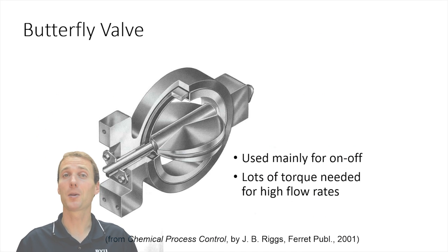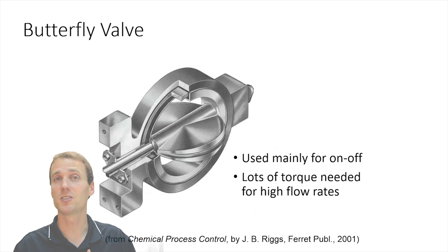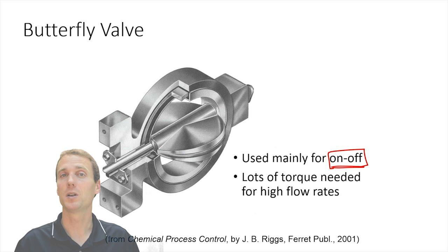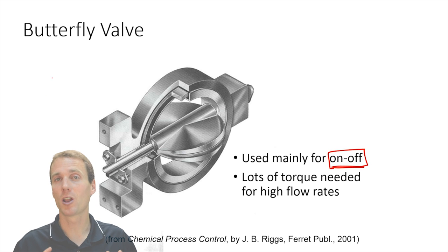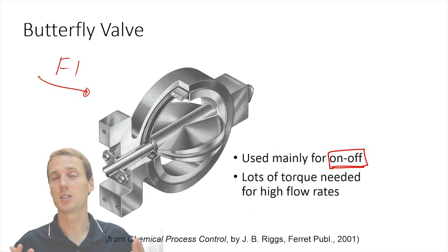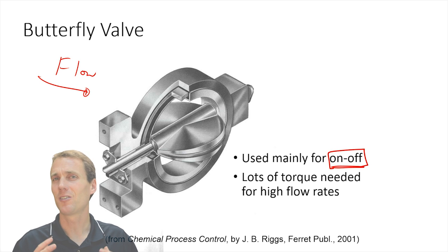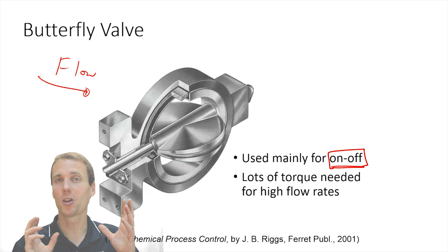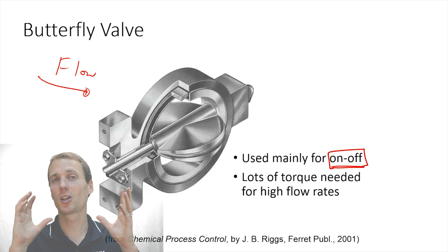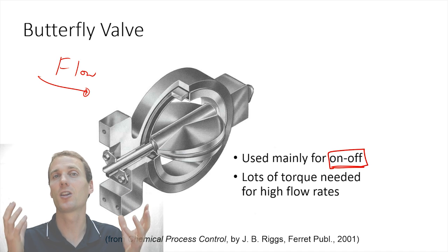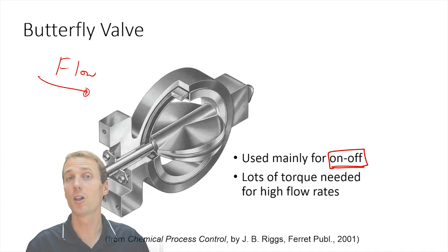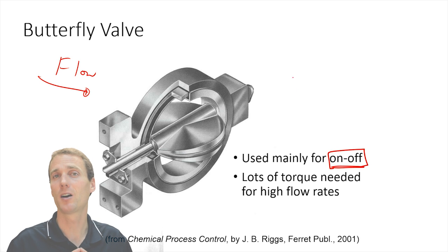Let's go on to a butterfly valve. A butterfly valve is very good for on-off type control. When it's fully open, there's very low frictional loss within the valve and we can achieve very low energy losses due to the valve. But then it will close very quickly and shut off the flow. If you had very fine control, as you close that valve just slightly, it's going to have a very large change in the flow that goes through that valve. So this one may not be the best valve for very fine-tuned control of a flow.